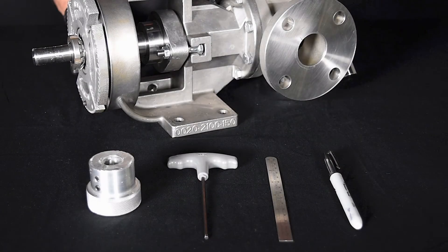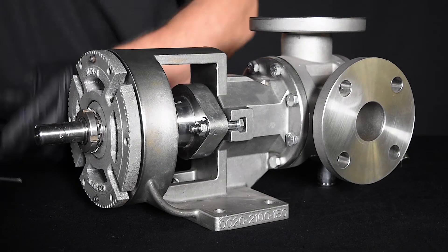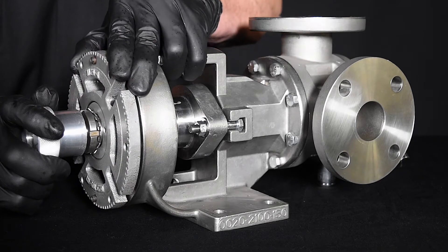Let's begin. Shown here will be the only tools you will be using for this process. Start by loosening the two bearing housing set screws in the face of the bearing housing flange enough so that they do not interfere with the bearing housing rotation during end clearance setting.